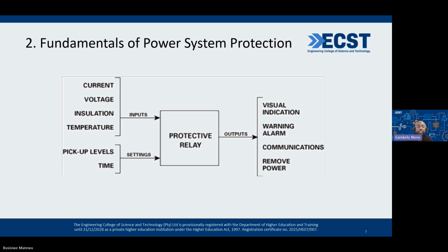As you see, there is an input of current, voltage, insulation, and temperature. Then there are the settings of the relay — your pickup levels, which act as your threshold — and also the time, which is how long the relay takes to respond to the fault.